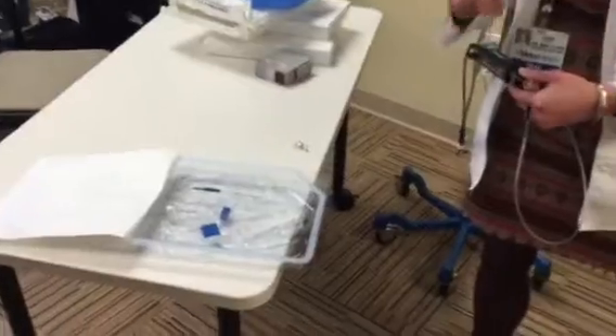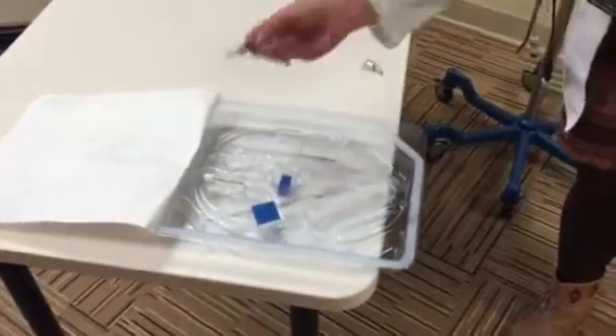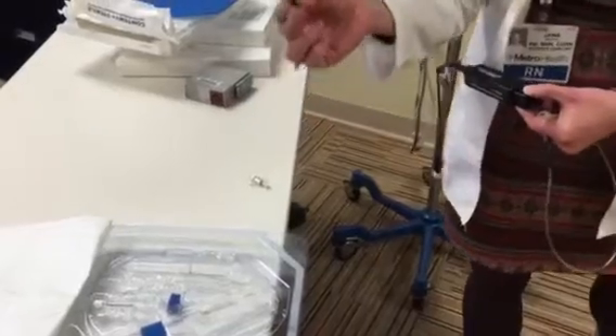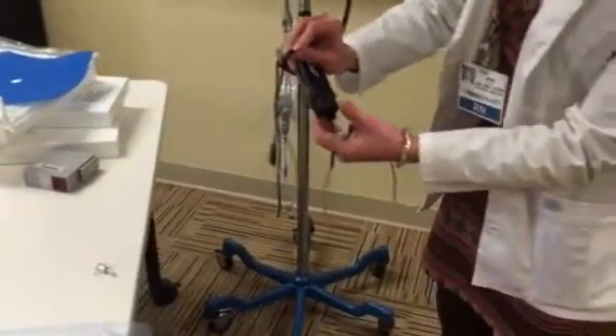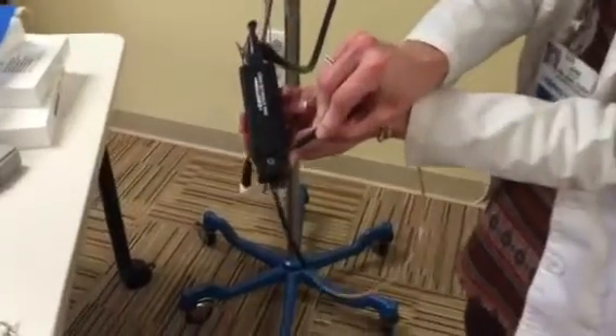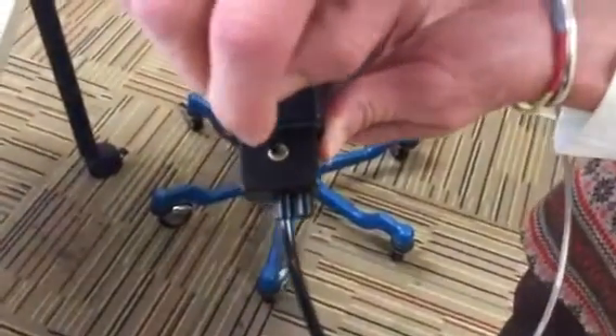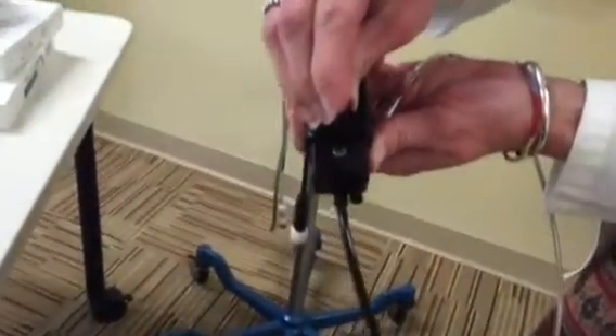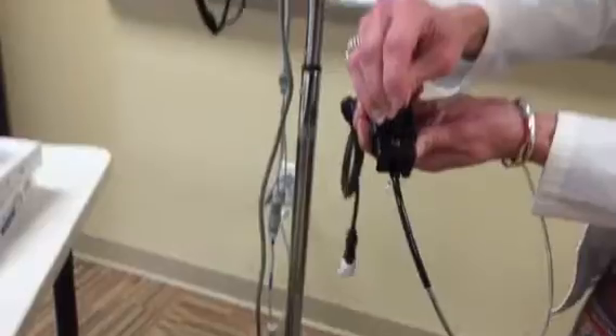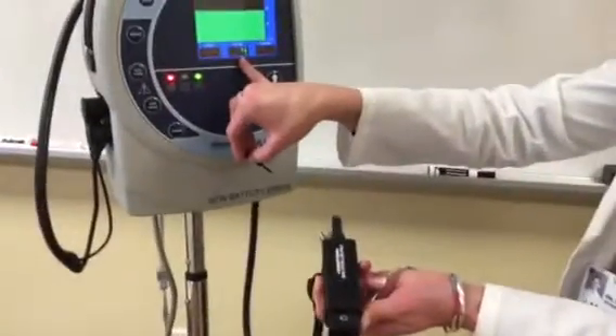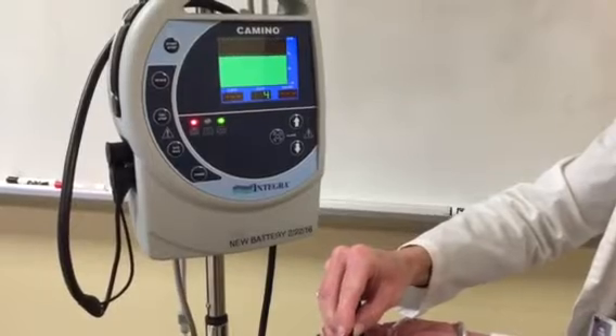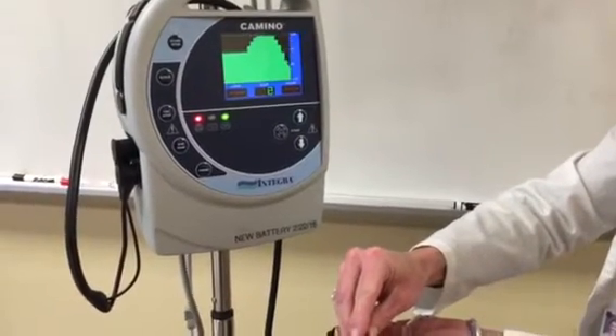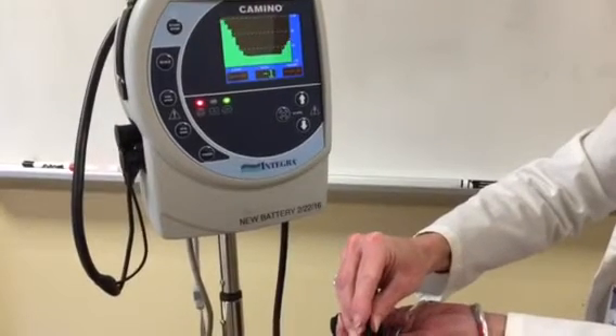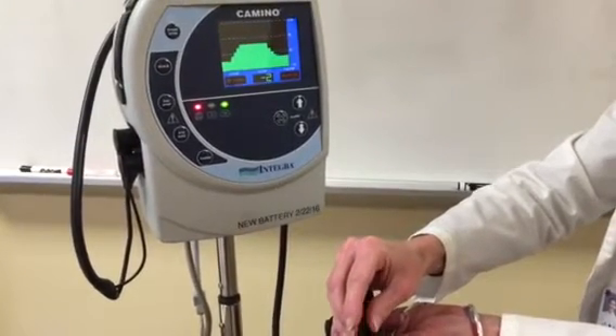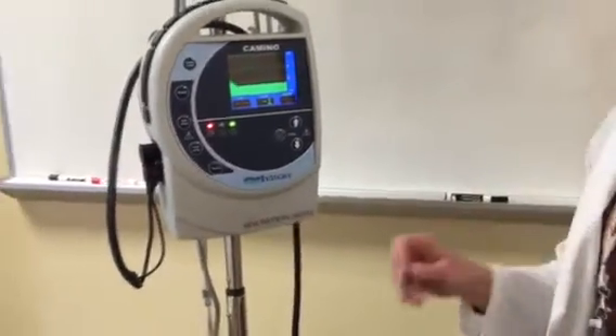Now we're talking about zeroing. So this has to be zeroed prior to insertion. This little screwdriver, also called a key, is what the physician will use to zero it. So at this little notch right here, this is where the key or screwdriver goes, and the physician will very gently turn this until, if you come up here and look at the Camino, we're trying to get this ICP right here reading 0. It's very, very fine movements. You can see I'm moving it very, very little, and it's moving quite a bit. So they'll work with this until they get that exactly at 0 before they put it in. We're going to pretend I got it to 0. So once that says 0, they are ready to insert it.